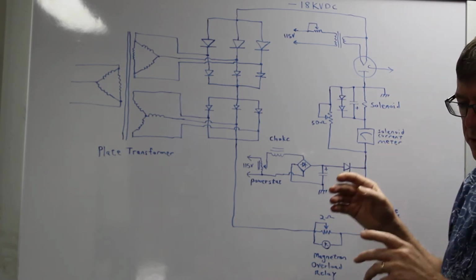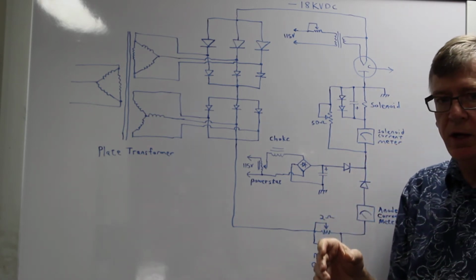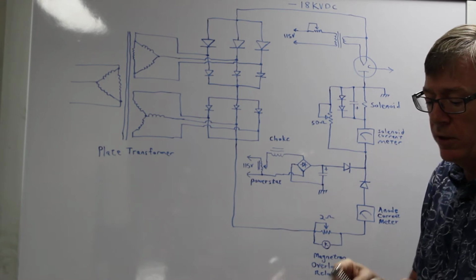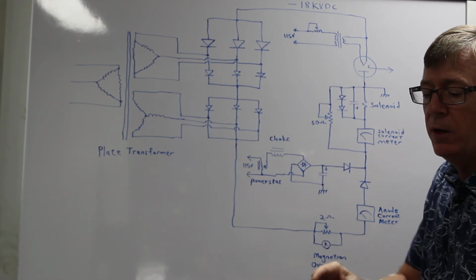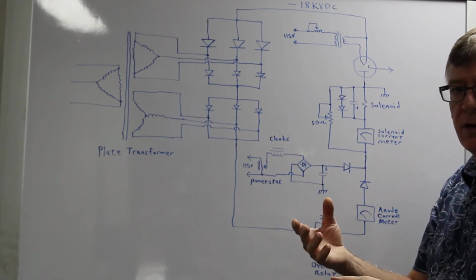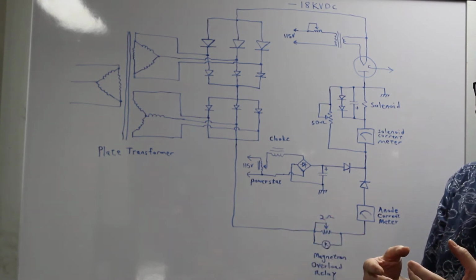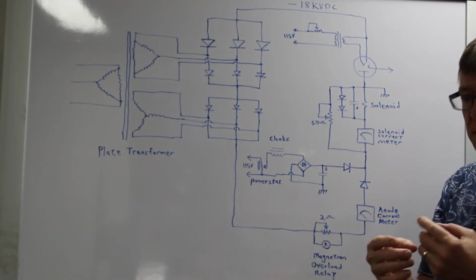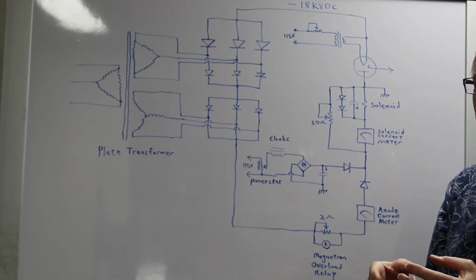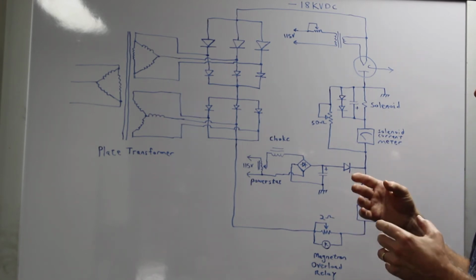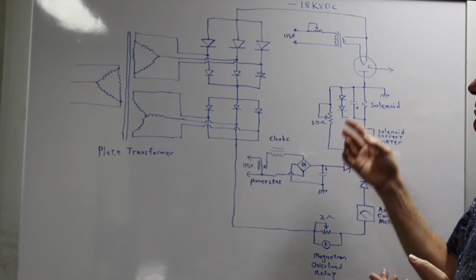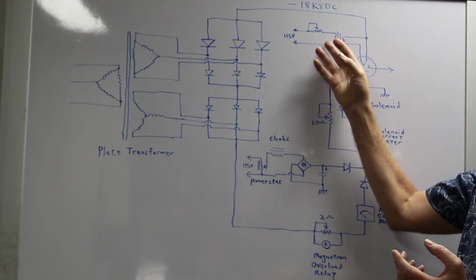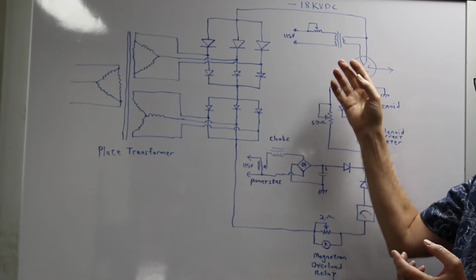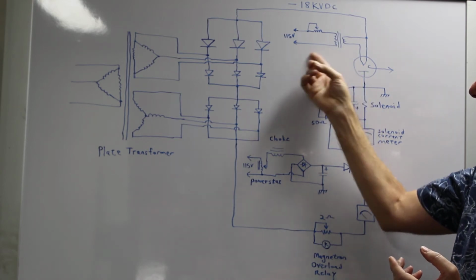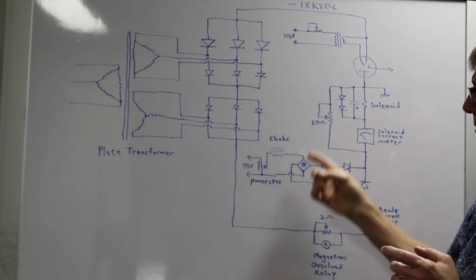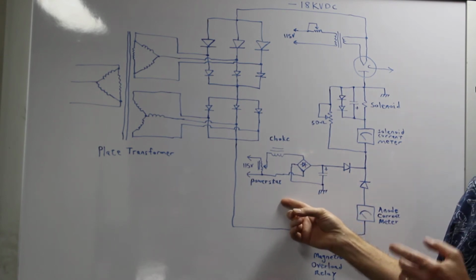Now, one of the other interesting things about how magnetrons work is that when they're radiating, the electrons come off of the filament and fly around in the tube, do their thing, and some of them come back and hit the filament again, and they cause it to get hotter because they release energy. The electrons release some energy into the filament. So we have to account for that and prevent the filament from getting too hot, and that's done via what we call a cutback, where we intentionally reduce the filament current in the filament supply in conjunction with decreasing the solenoid current to increase the power.